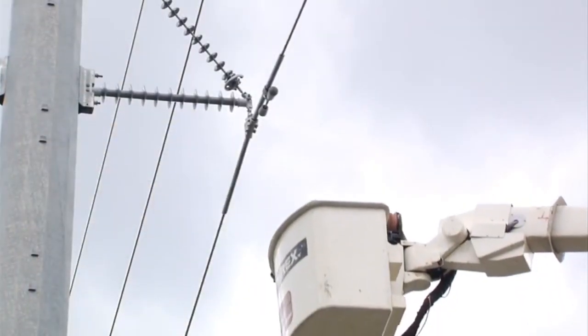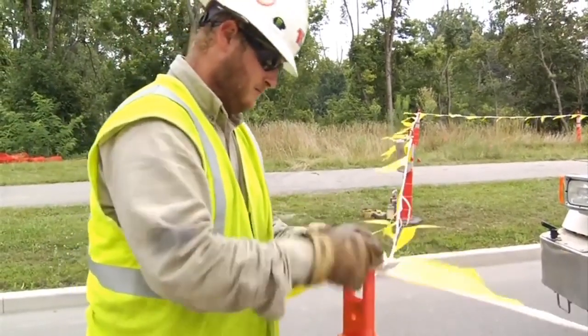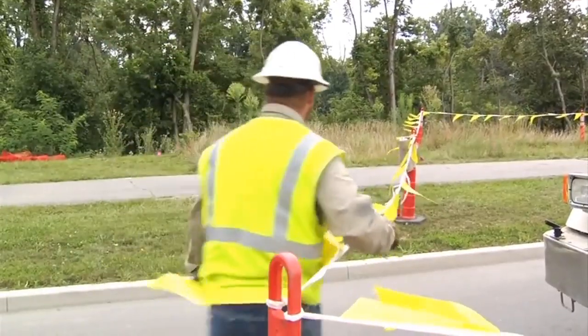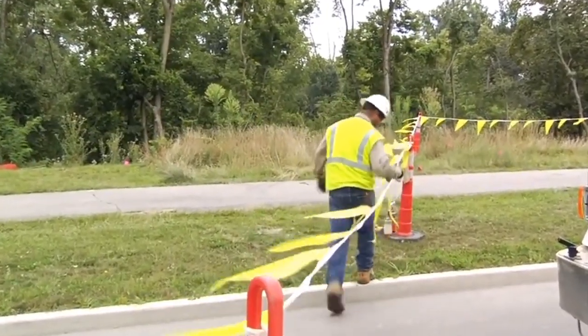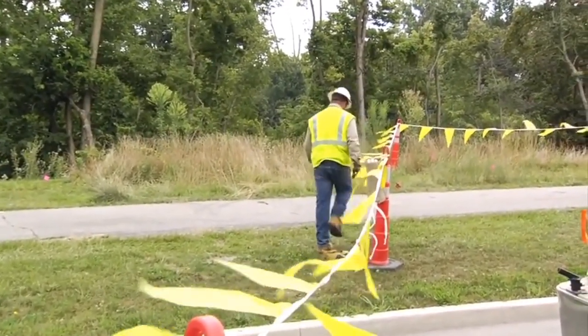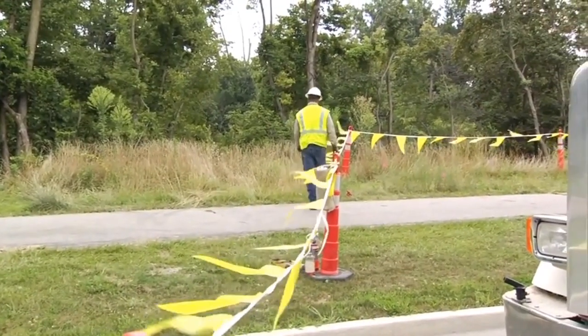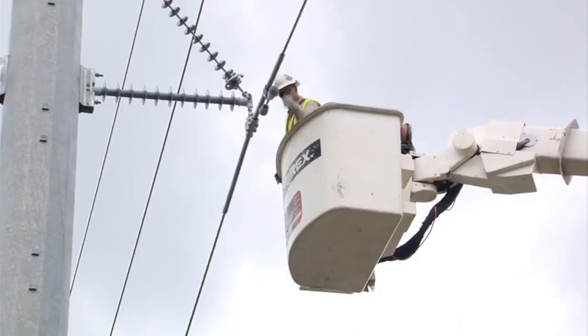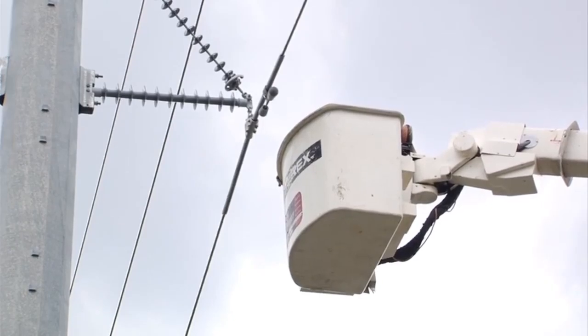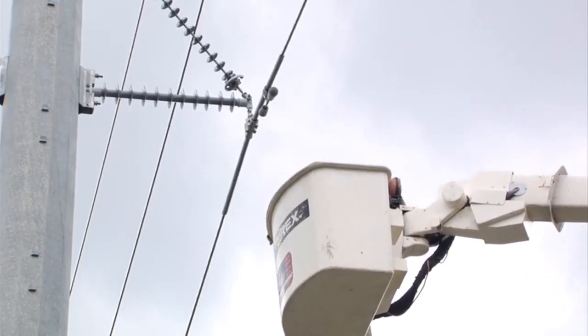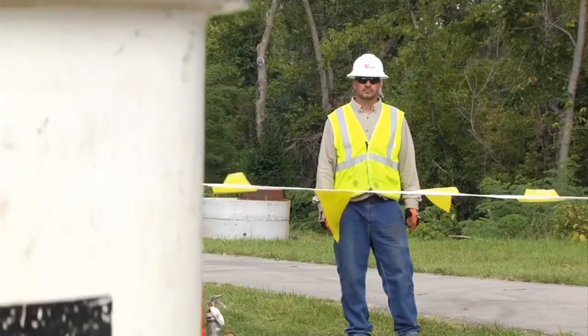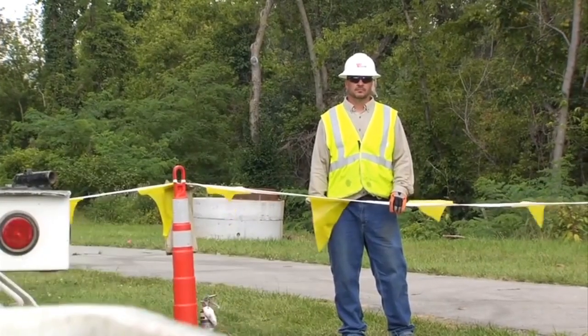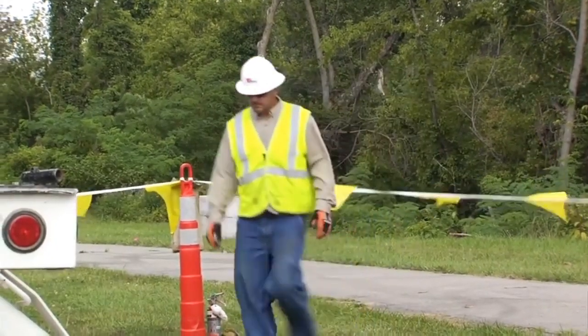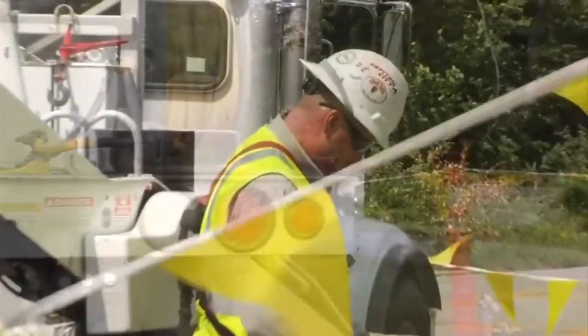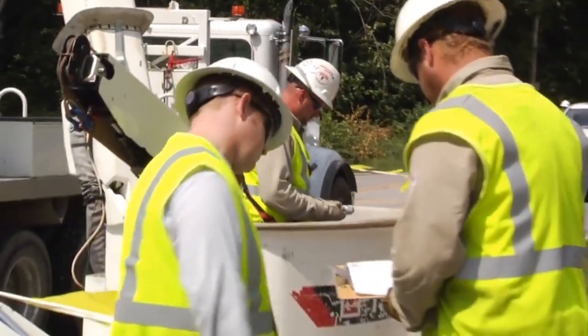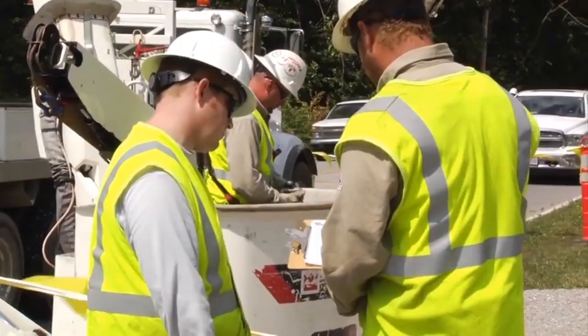Aerial devices shall be barricaded to protect workers on the ground from falling objects or touching the aerial device if it accidentally contacts energized conductors. The barricaded area shall also be extended beyond any temporary ground rod or anchor. When the barricaded area needs to be entered, the observer shall confirm that all work aloft is stopped and that the bucket, work platform, or boom has been moved out to a safe distance from nearby energized conductors or sources. Work will only restart after the observer has confirmed that the barricaded area is clear.